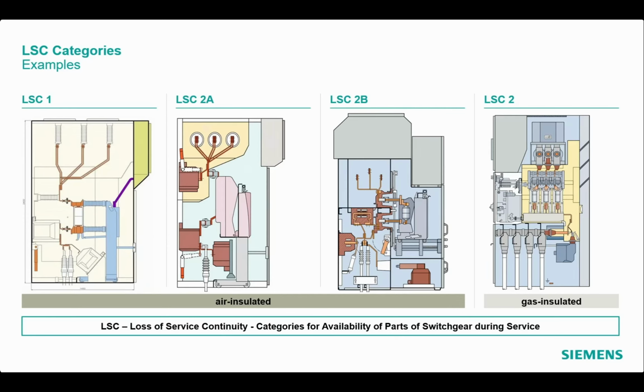On the extreme right, one can refer to the category LSC2, which is a category especially applicable for gas-insulated switchgears, allowing maximum continuity of service. For example, here it is possible to open the connection compartment while keeping the bus bars live. In case of LSC2A category, one can see in the picture that the bus bar compartment is segregated from the rest of the compartments, thus providing only a limited service continuity.